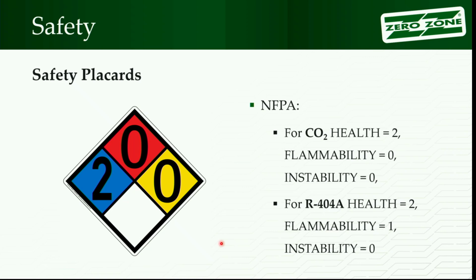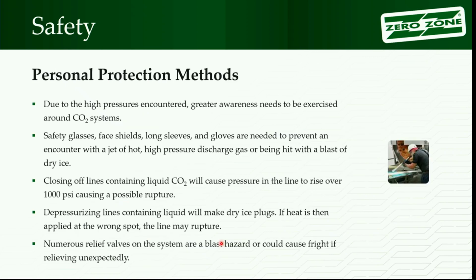So a big thing comes down to personal protection. What are you guys doing to protect yourself when you're on a job site? Again, respecting our refrigerant. So you do have higher pressures. If you have a leak, there's more likelihood you can spray oil across the room or near your body compared to other refrigerants, just with the higher pressure.